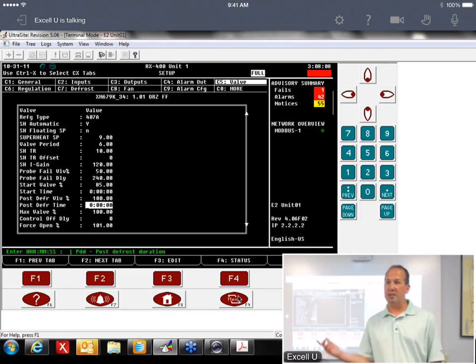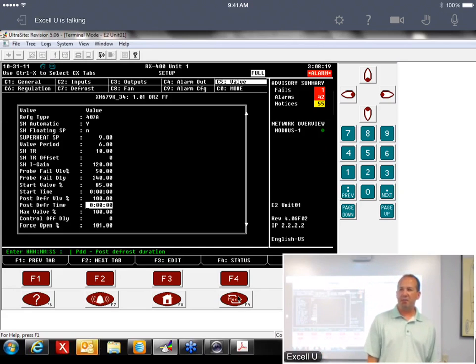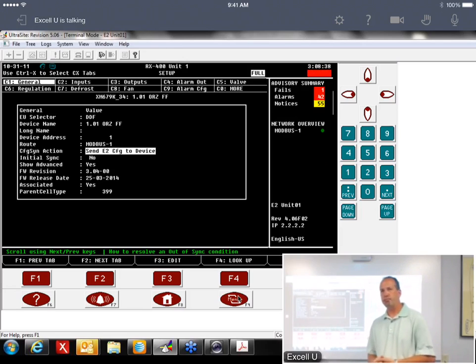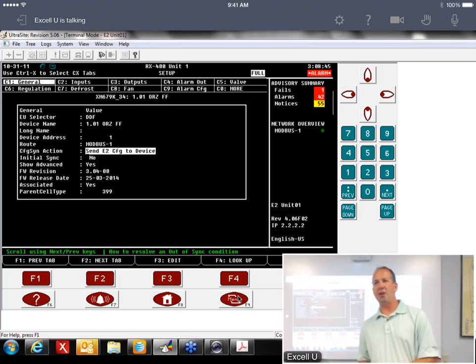I've got some stores, early on, before this even was out, where they didn't know how to fix it, and the store personnel just got used to it. It's for a split second it goes off. But for those that want it changed, you just go to this config sync action and reverse that action, and that'll stop it. There's no issue with that as long as you do it a week after startup. But you've got to remember, if you replace your module, change it back.